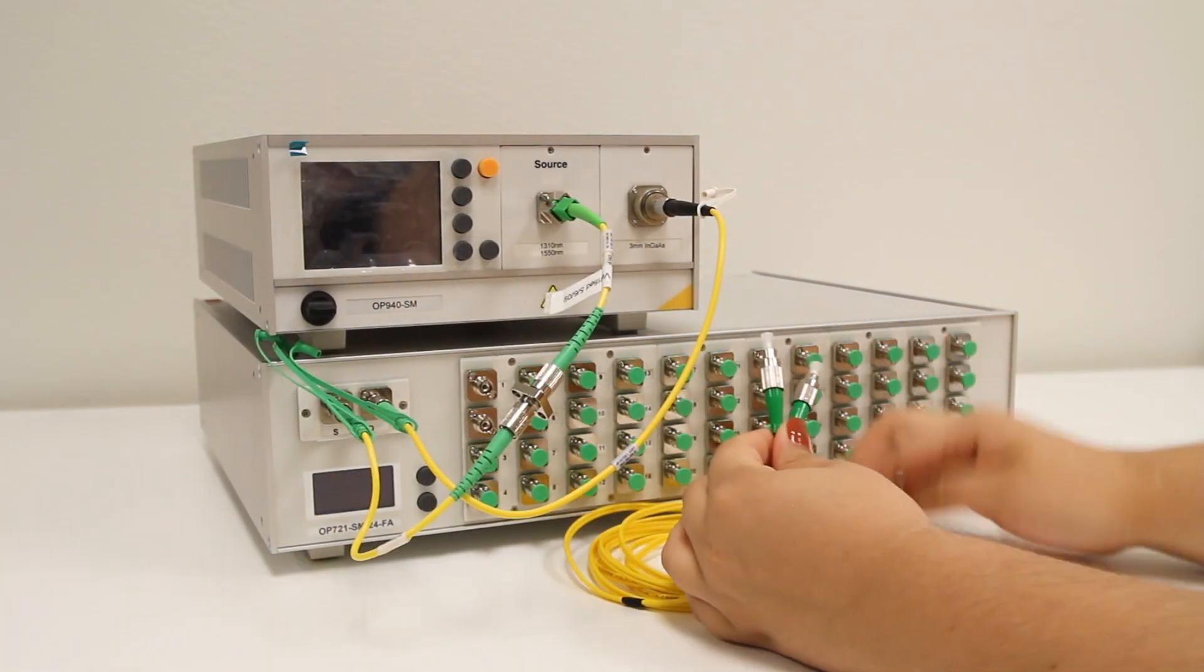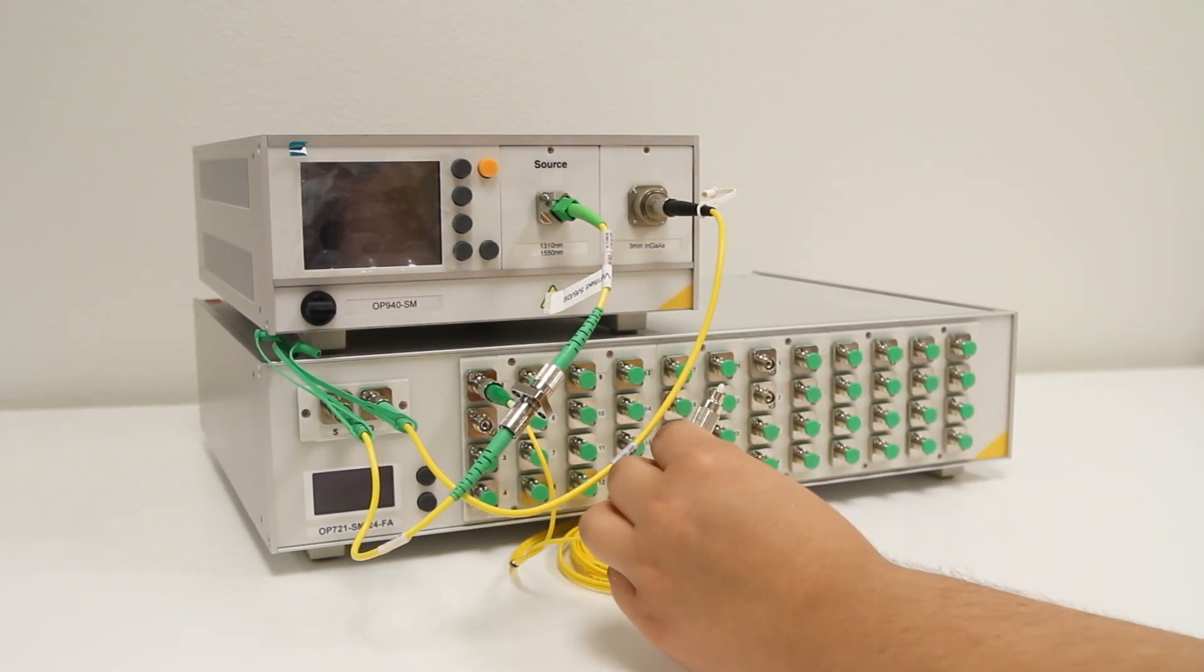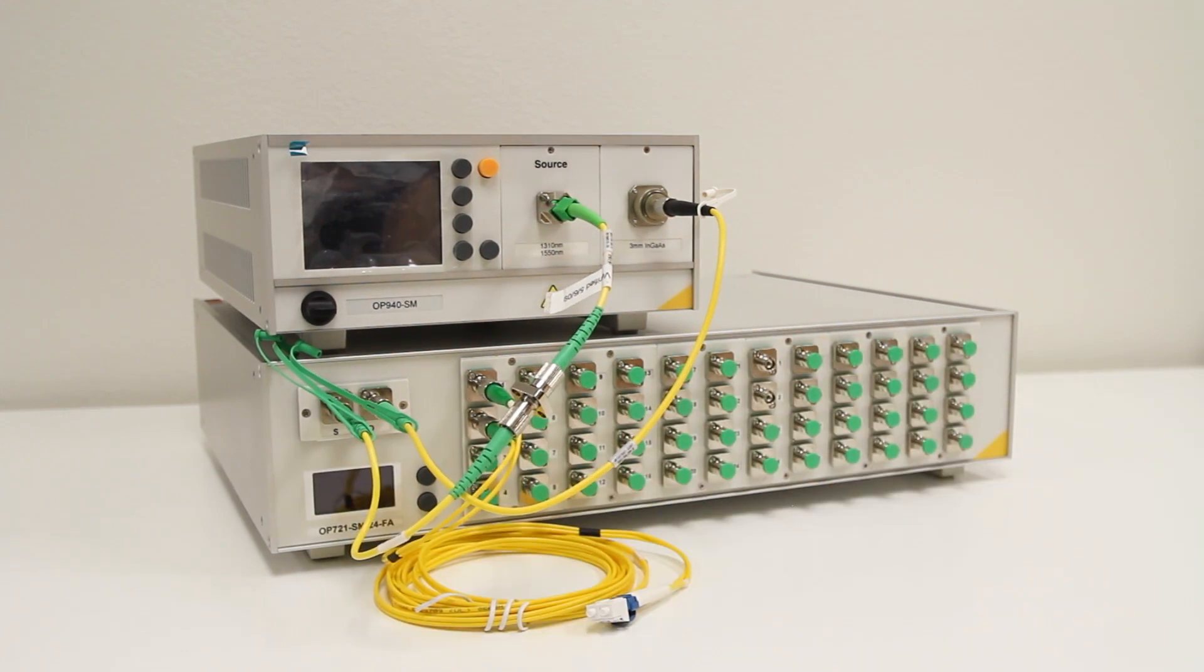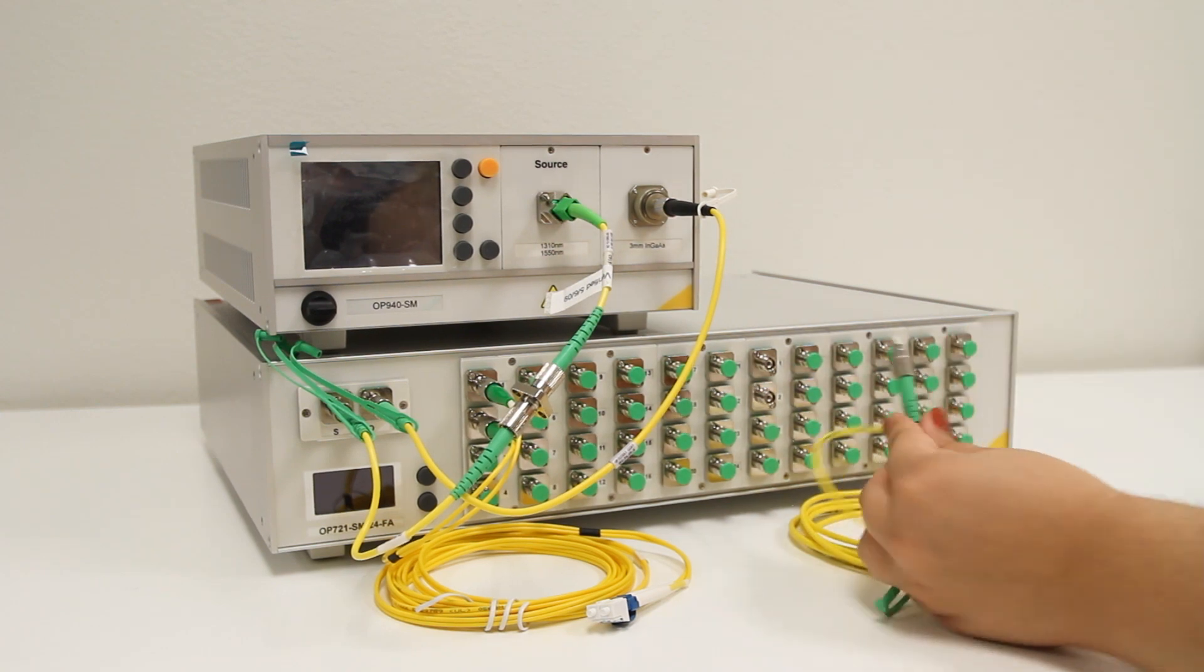With the units connected to each other, the reference cables are now connected to the switch. This OP721 is 24 channel, meaning that there are 24 channels available in each direction, for a total of 48 connectors at the front panel. Here, we connect to channels 1 and 2 on each side.